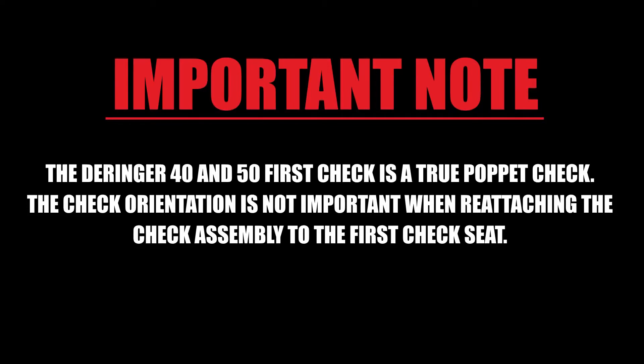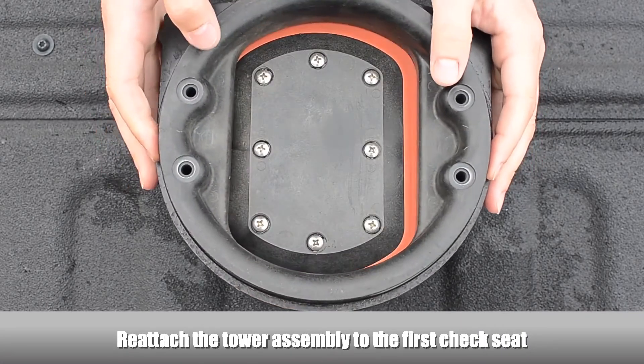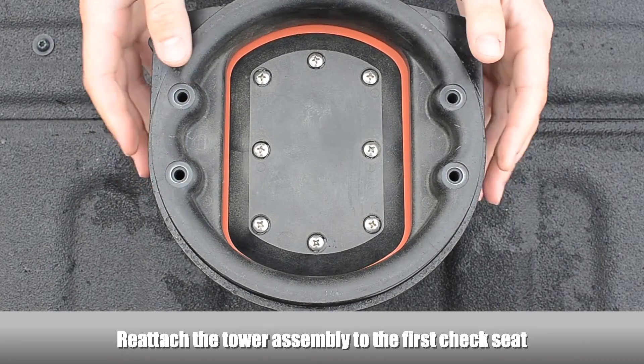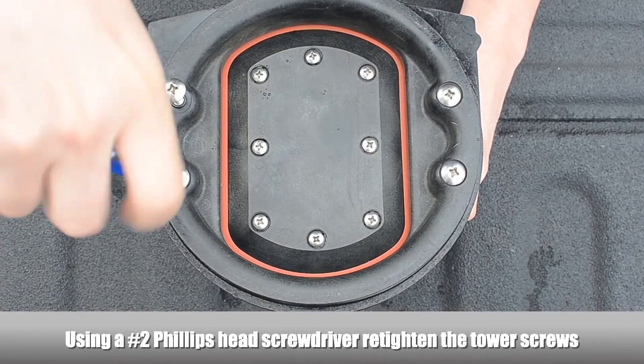The Deringer 40 and 50 first check is a true poppet check. The check orientation is not important when reattaching the check assembly to the first check seat. Reattach the tower assembly to the first check seat and, using a Phillips-head screwdriver, re-tighten the tower screws.